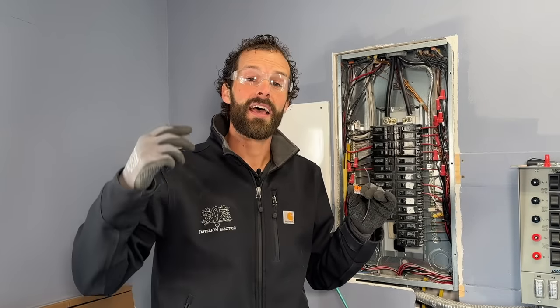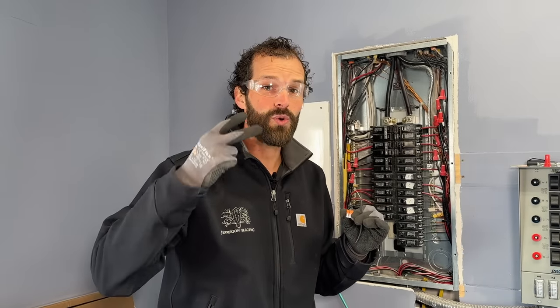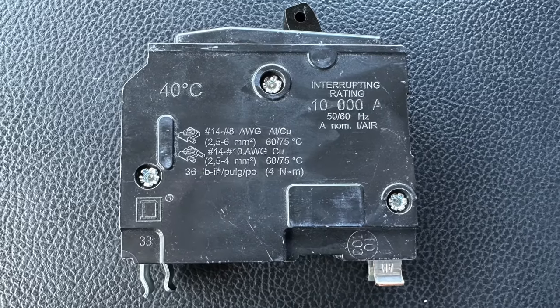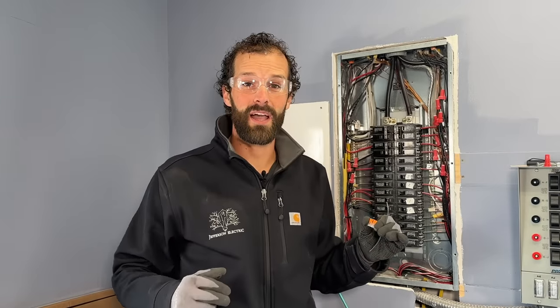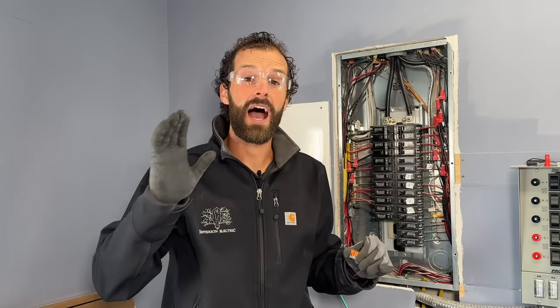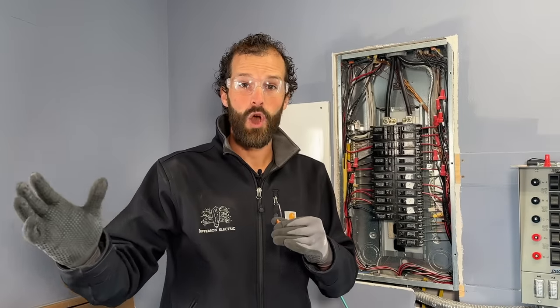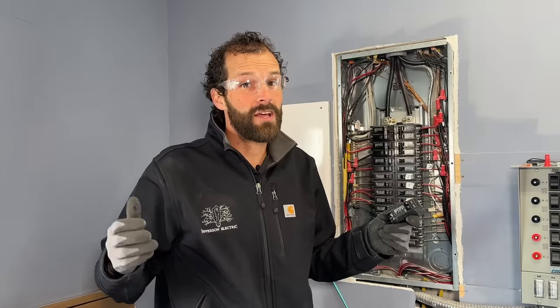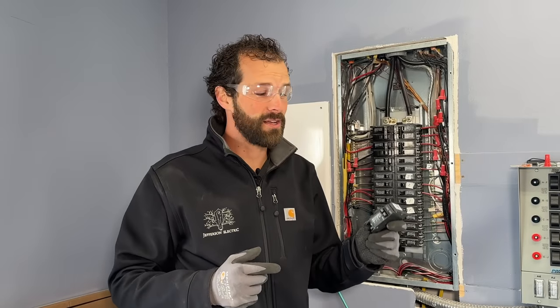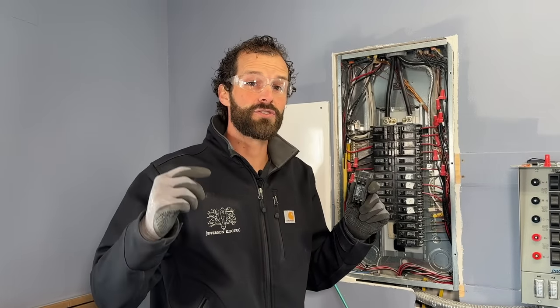Option one is using a pigtail properly sized to your circuit and a Wago 221 lever nut — the least intimidating option if you're a homeowner. Option two: if you've got a Square D panel, unlike my Eaton panel, Square D panels allow for two conductors per breaker in some common instances — both Homeline and Square D QO. If you've been called out by a home inspector for this, they often blanket-call it as a violation. However, you can prove it by going to the manufacturer's website, pulling the data sheet, which will list the number and size of conductors that breaker is rated for.